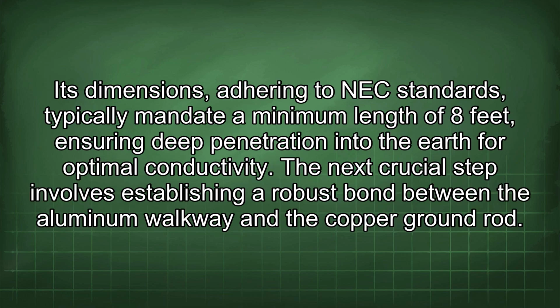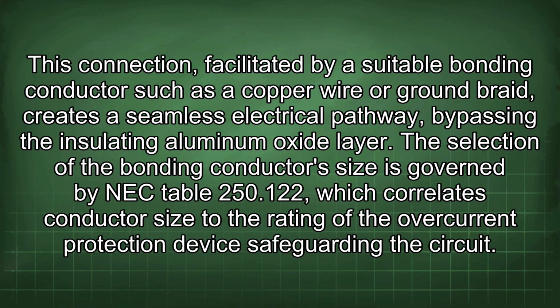Its dimensions, adhering to NEC standards, typically mandate a minimum length of 8 feet, ensuring deep penetration into the earth for optimal conductivity. The next crucial step involves establishing a robust bond between the aluminum walkway and the copper ground rod. This connection, facilitated by a suitable bonding conductor such as a copper wire or ground braid, creates a seamless electrical pathway bypassing the insulating aluminum oxide layer. The selection of the bonding conductor size is governed by NEC Table 250.122, which correlates conductor size to the rating of the overcurrent protection device safeguarding the circuit.